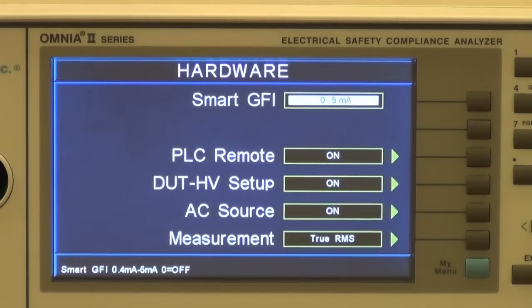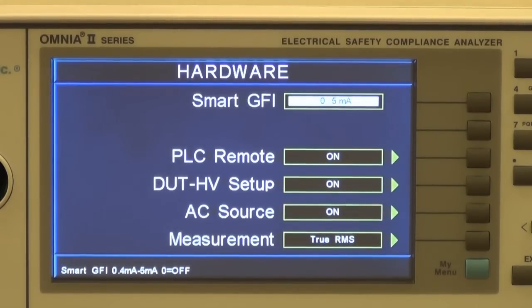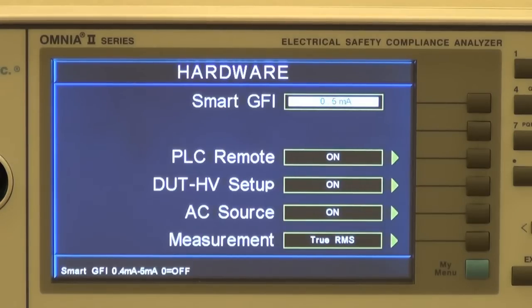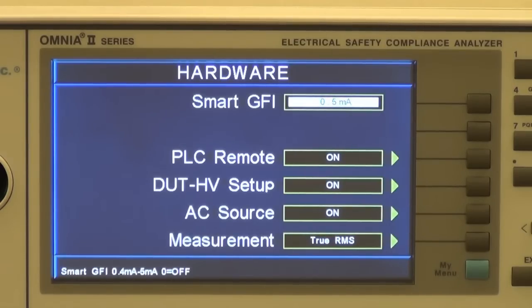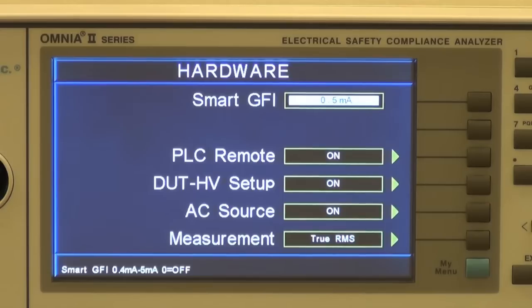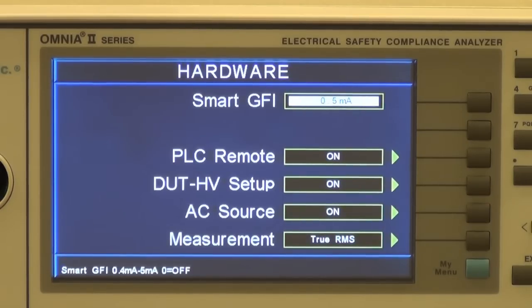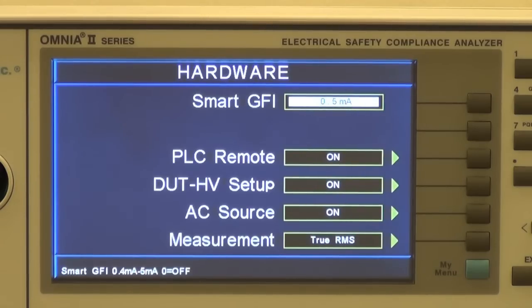The Omnia II gives the user the capability to select the measurement method for the dielectric withstand test. From the hardware settings screen, press the measurement soft key. As the soft key is pressed, the measurement method will toggle between true RMS and average. If you have an 8206, 8256, 8207, or 8257 unit, you will have access to the DUT/HV setting.